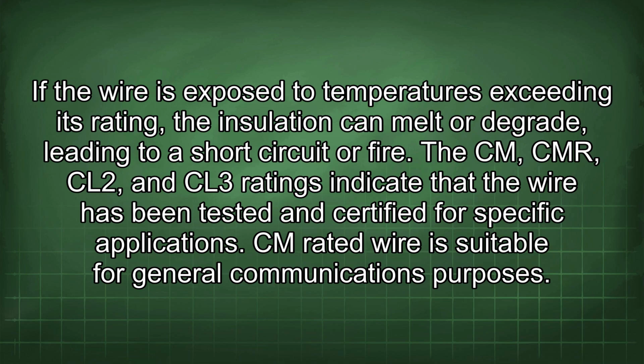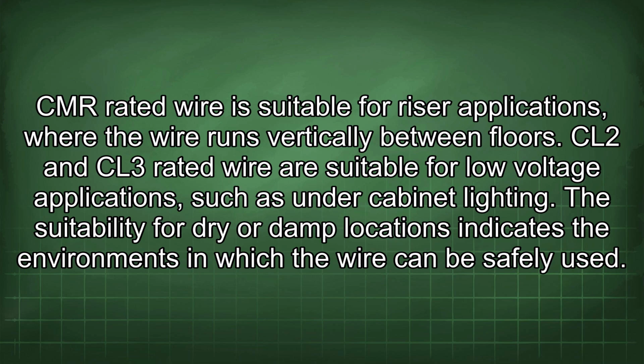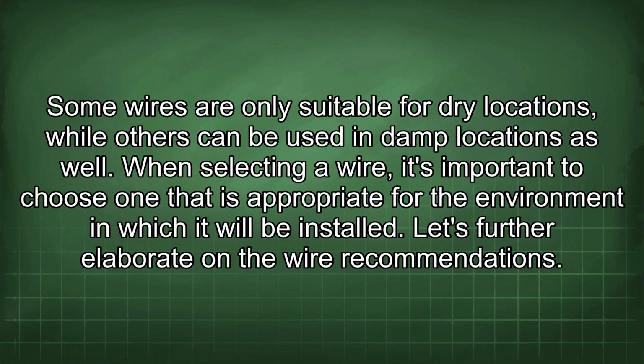The CM, CMR, CL2, and CL3 ratings indicate that the wire has been tested and certified for specific applications. CM-rated wire is suitable for general communications purposes. CMR-rated wire is suitable for riser applications where the wire runs vertically between floors. CL2 and CL3-rated wire are suitable for low-voltage applications, such as under-cabinet lighting. The suitability for dry or damp locations indicates the environments in which the wire can be safely used. Some wires are only suitable for dry locations, while others can be used in damp locations as well. When selecting a wire, it's important to choose one that is appropriate for the environment in which it will be installed.